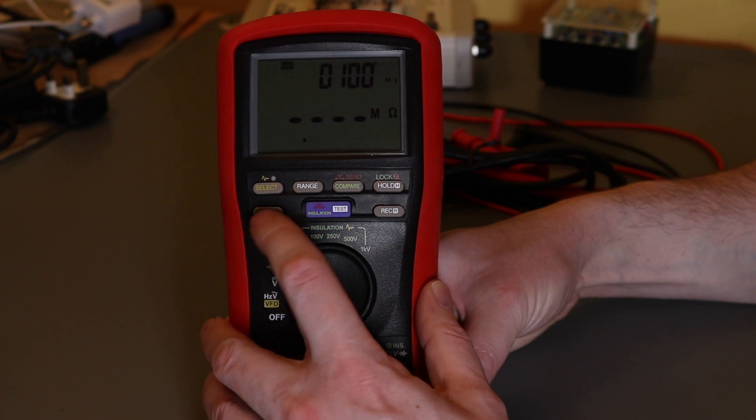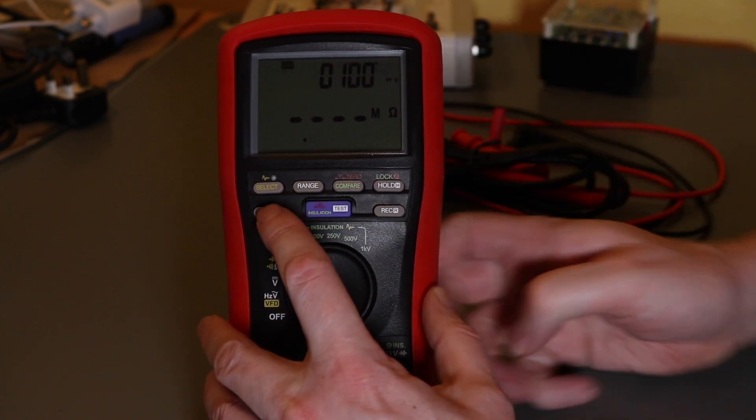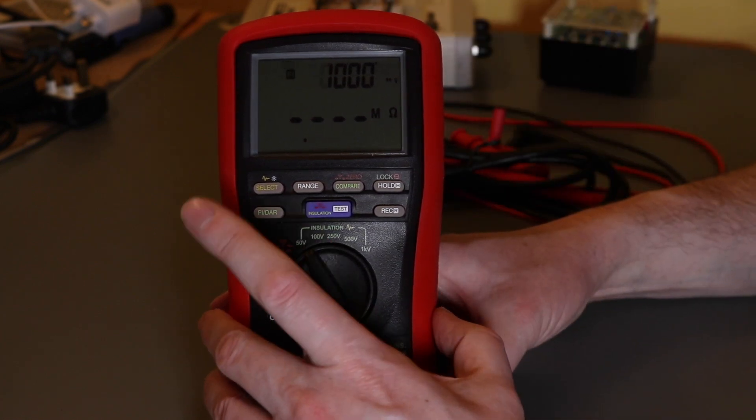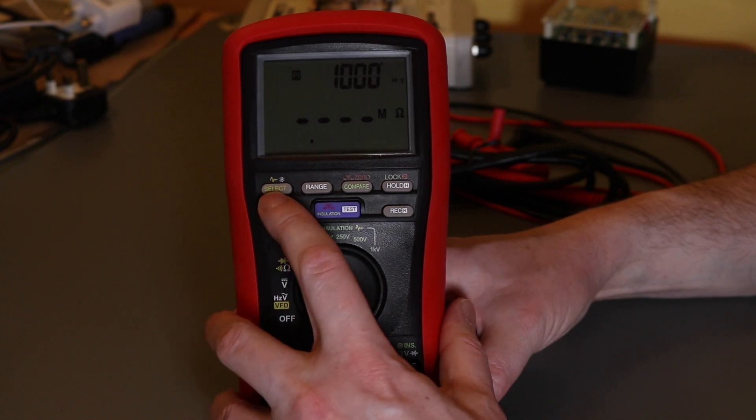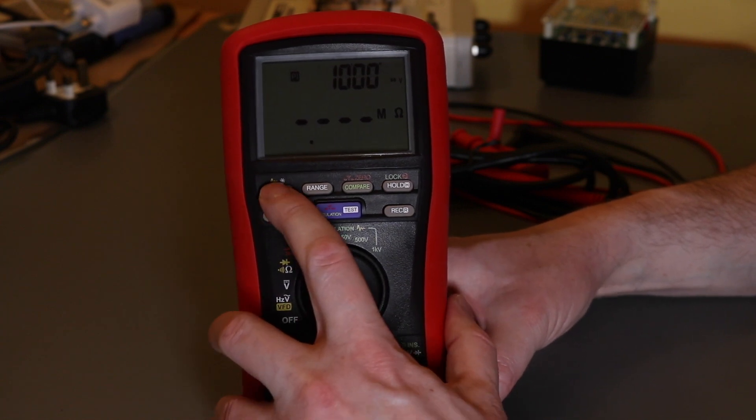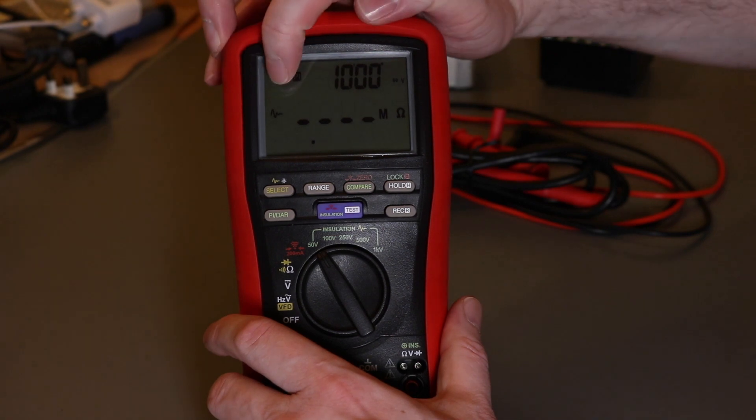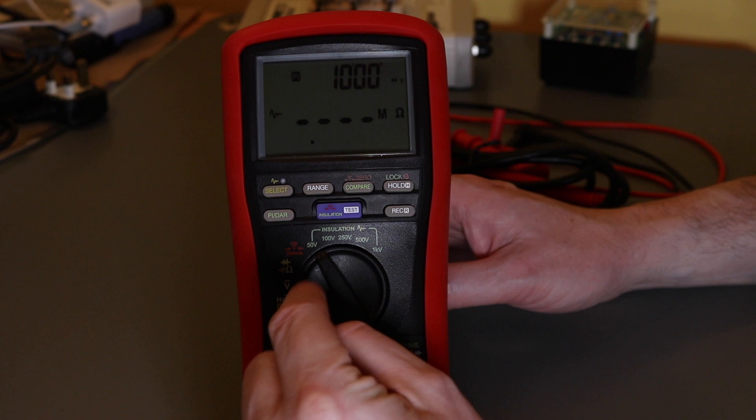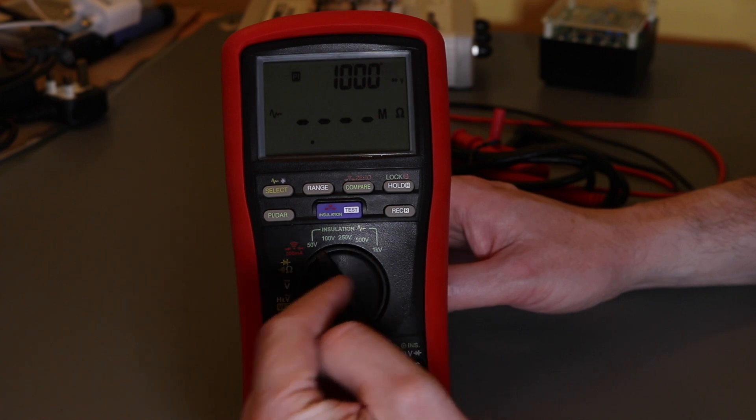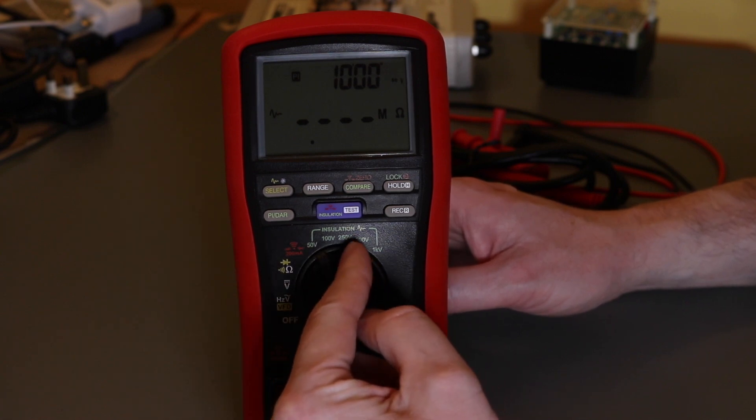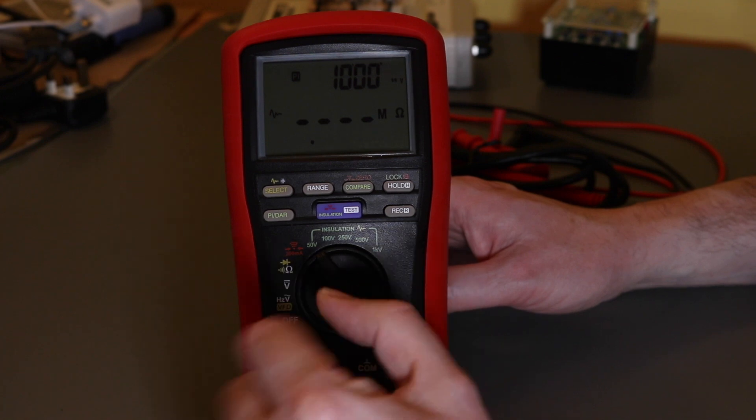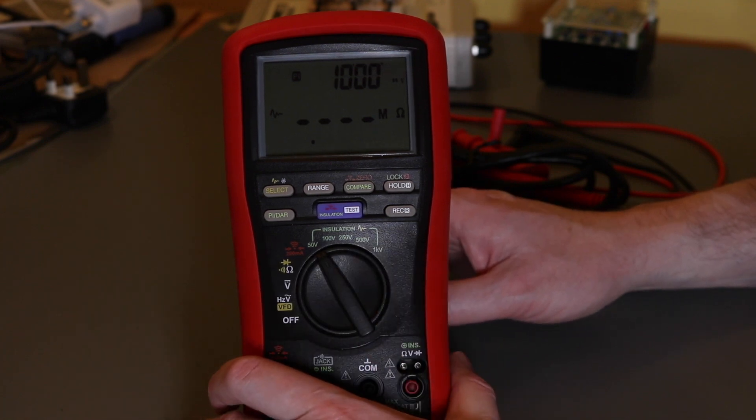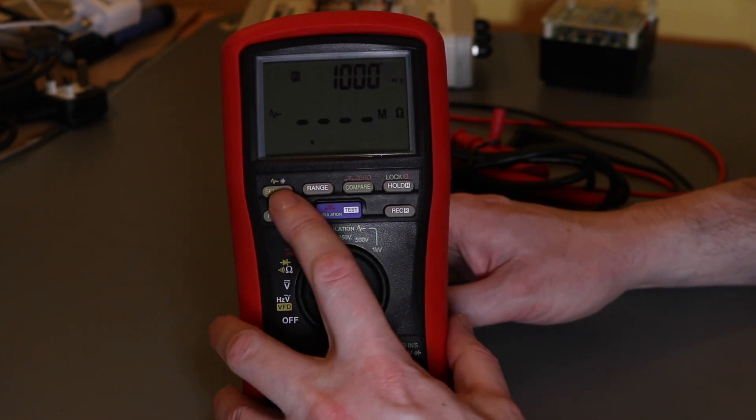Alongside for use in the insulation you have PI and DAR ratio tests, PI first and then DAR. Timer comes up at the top when you move to those functions. You also have a smoothing function. Smoothing is probably not much use on the 50, 100, 250 to 500 ranges because they only go up to 500 megaohms max, but the 1kV range can go up to 25 gigaohms, so it might be useful on that function.